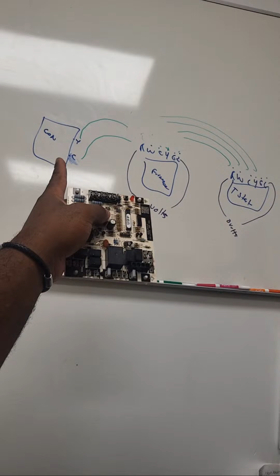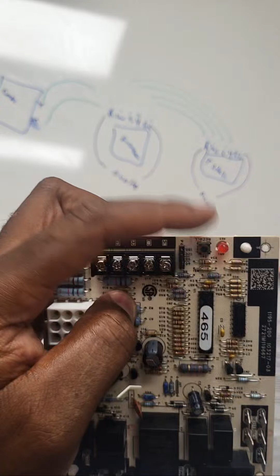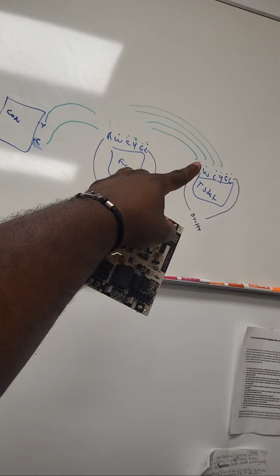I have my thermostat wires going into my circuit board, and my 24 volt wires from my condenser going to my circuit board. So I took everything off, reset the fuse popper, turned power on, and my light stayed on. If this didn't work, the fuse popper would have popped right back up, but that didn't happen. So at least I knew the board was okay, but something was going on either with my indoor thermostat wires or my outdoor thermostat wires.